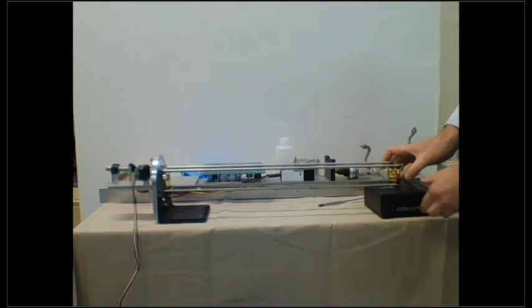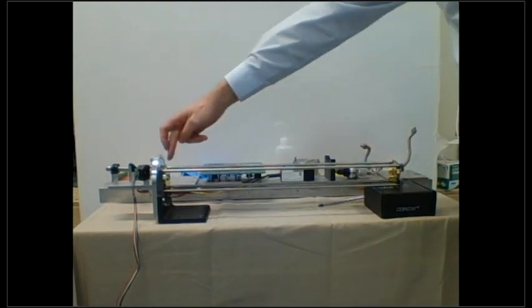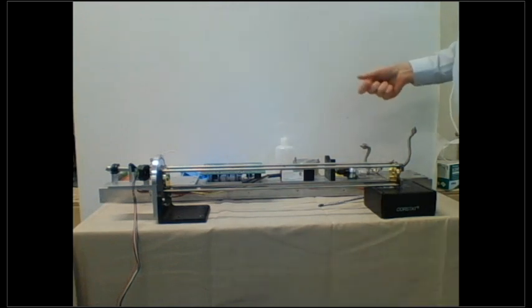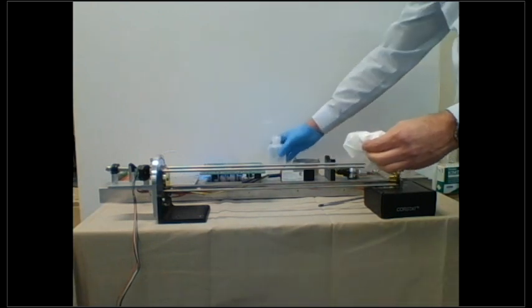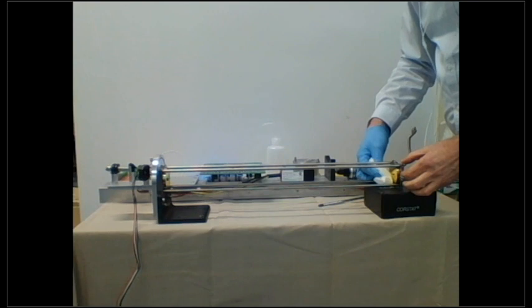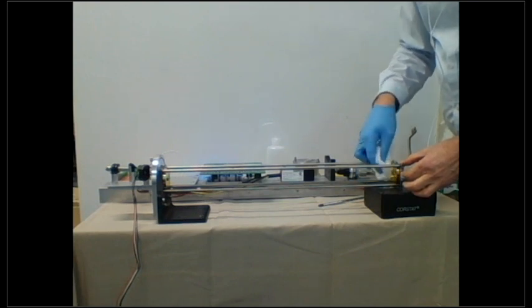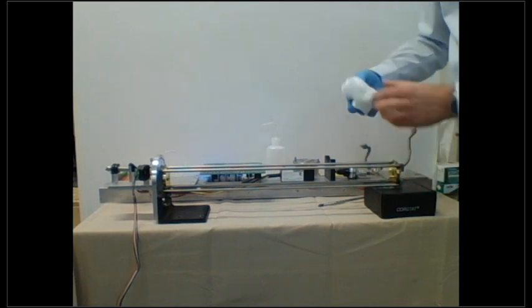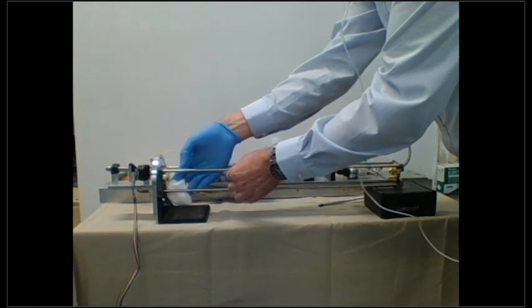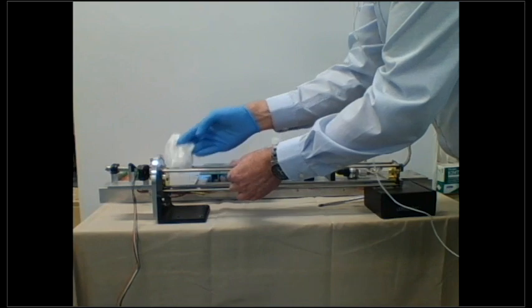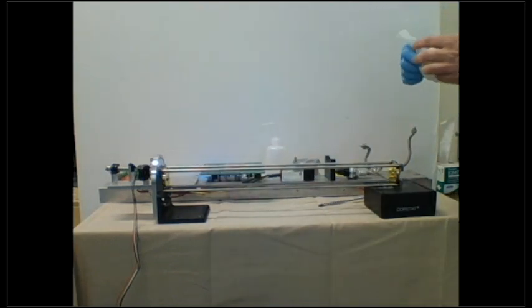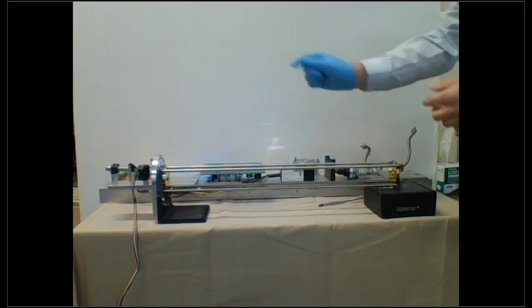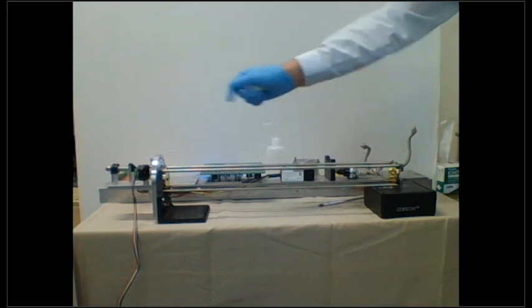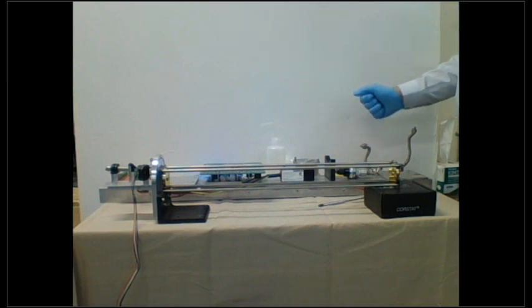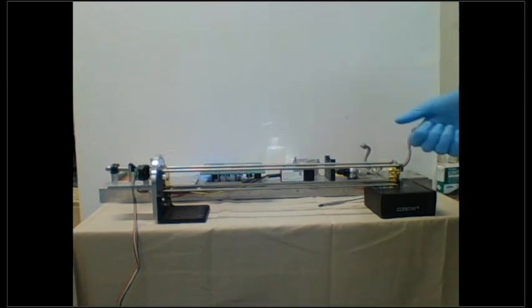If anything gets on those mirrors, they're relatively easy to clean. You can just simply use some Kimwipes or some other kind of lint-free wipes. You can use some methanol. Simply wet the wipe and then just simply apply it gently to the mirrors themselves. Give them a good little cleaning. Any debris, dust, that sort of thing should be able to come off. And if you have some compressed air or a can of compressed air, you could give them a little spritz of air to evaporate off the methanol and to get rid of any dust particles or anything that's on the cell.